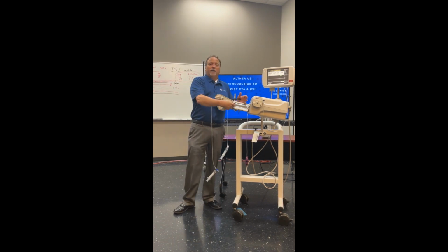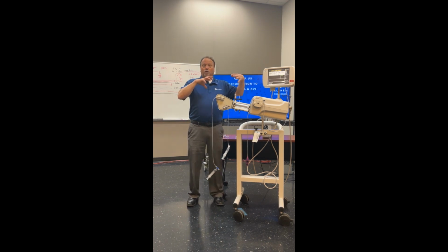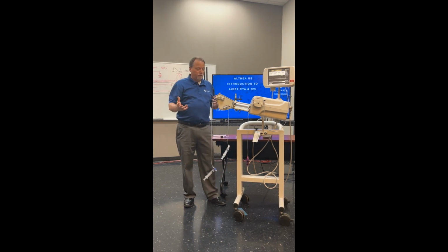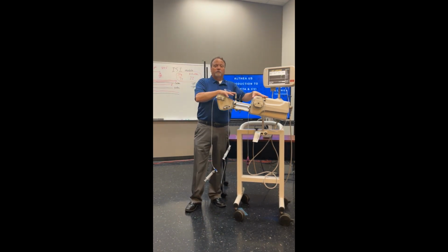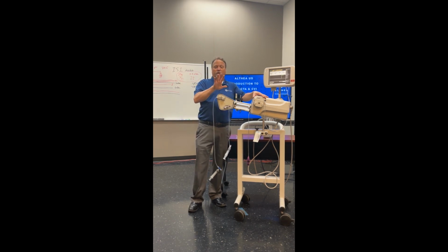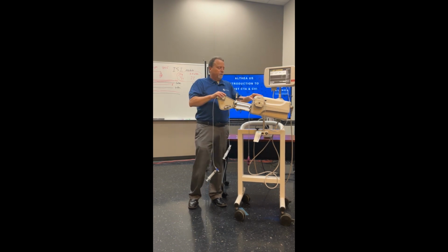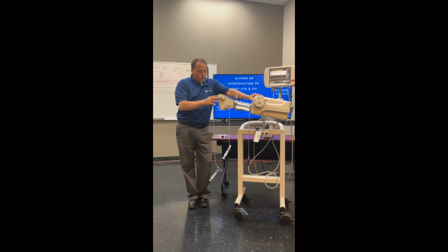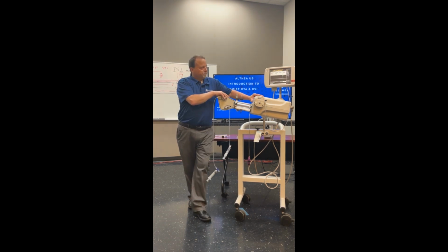Since this is automatic fill and you don't have to break the, I'm going to call it the seal to the patient, one set of disposables for the injector can be used for up to 5 patients. After 5 patients, you have to remove them and install new disposables. So again, it's a cost saving. Instead of having to replace syringes all the time, you can use them for up to 5 patients.